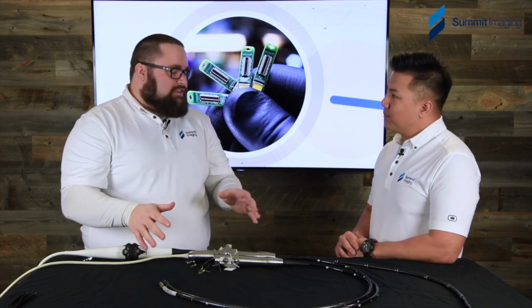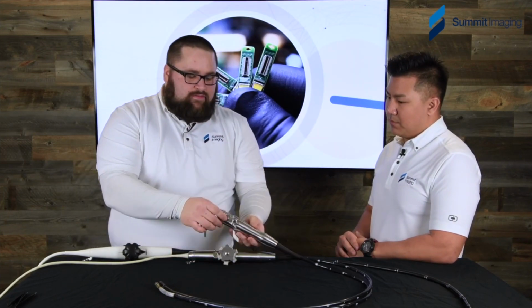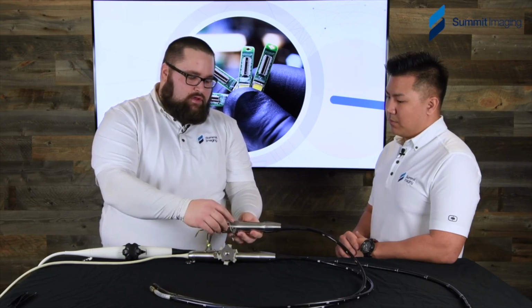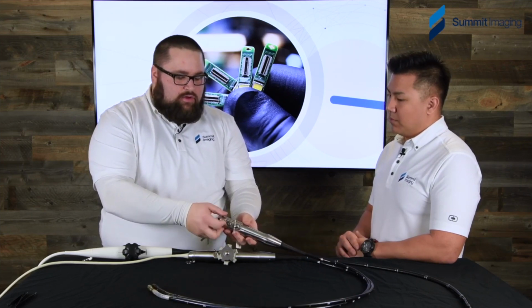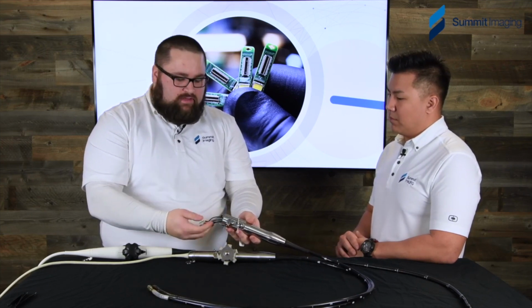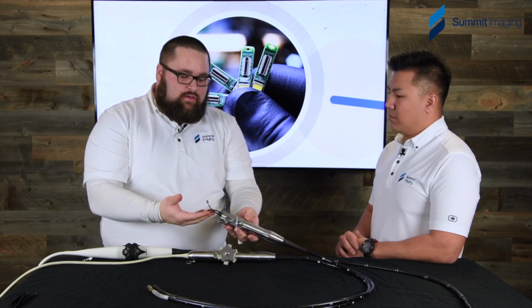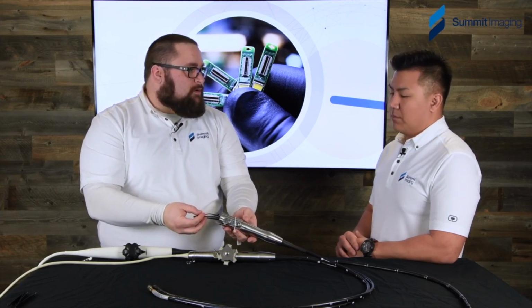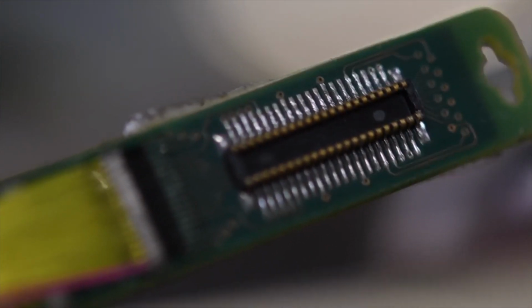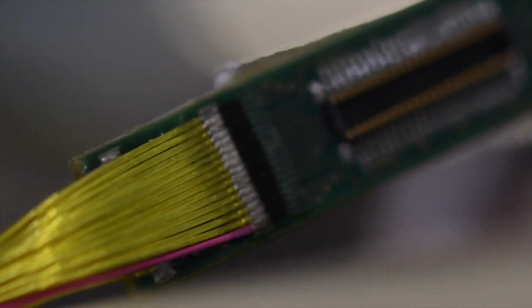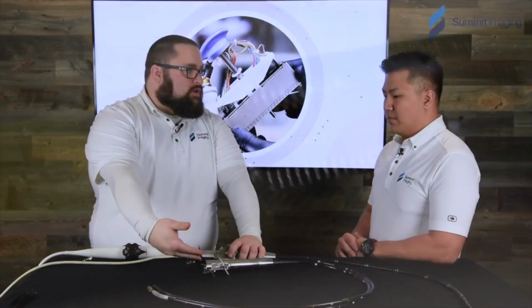You've got a couple seconds to figure it out, but you'll have your steering mechanisms, your controls for the tip, usually a lock for your steering mechanism, but inside of that handle is all the lines going down south to the tip. And this is where I see a lot of problems happen on our discovery reports that we do for our customers: fluid has gotten into this handle and it's shorted out these connections right here.